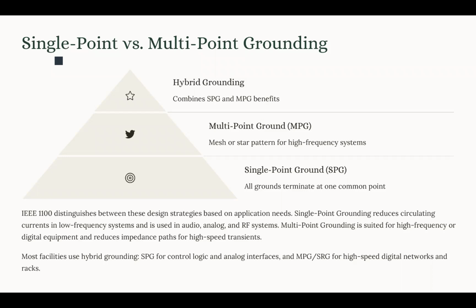It reduces the radiated emissions and susceptibility to external EMI by providing that low impedance return path. But this multi-point grounding also has its own limitation. One would be the circulating current possibility. So when we have a low frequency, that MPG, that multi-point grounding, can create ground loops, which introduces the noise into the analog systems.